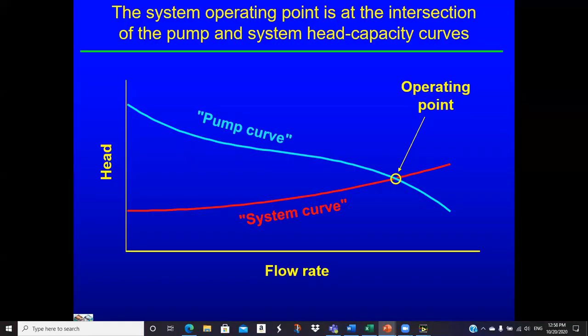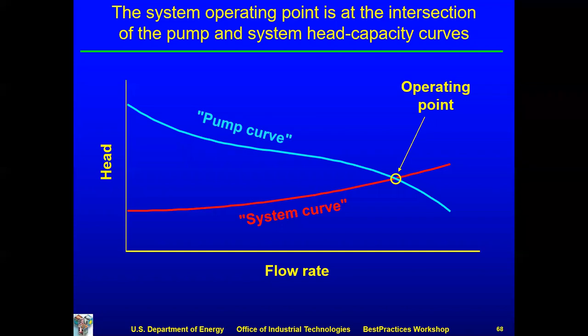Okay, so we get a pump curve from the manufacturer. We get a system curve from our analysis of the system, and we plot them up on the same graph. Wherever they cross, that's where we're going to operate.